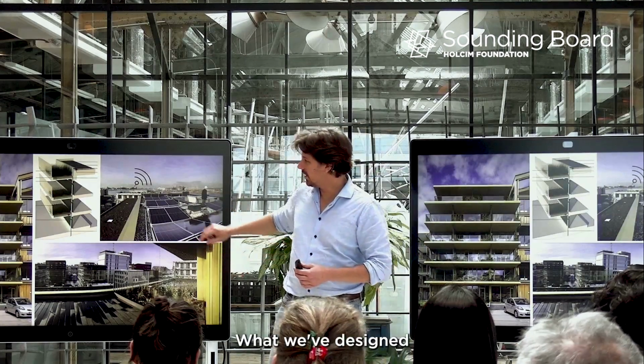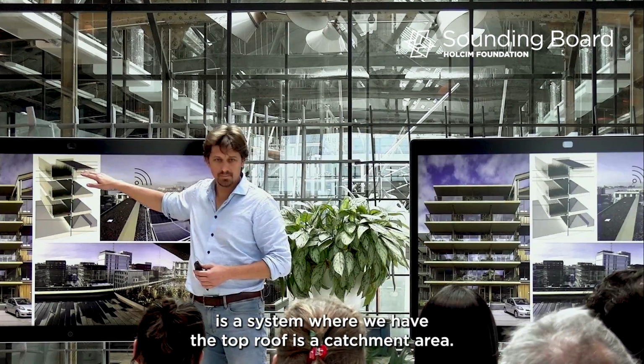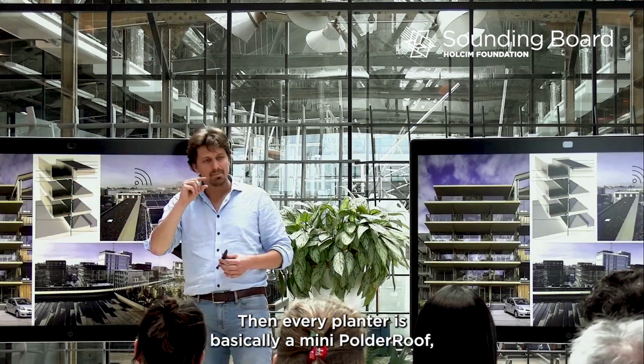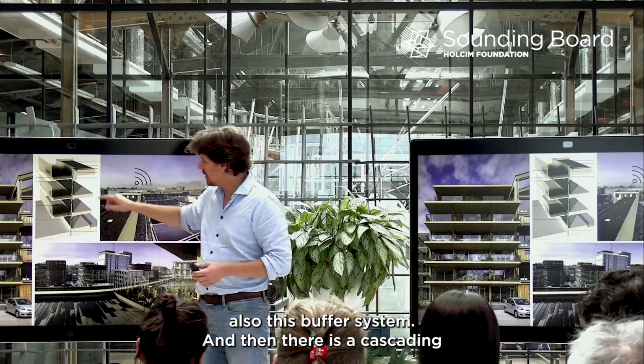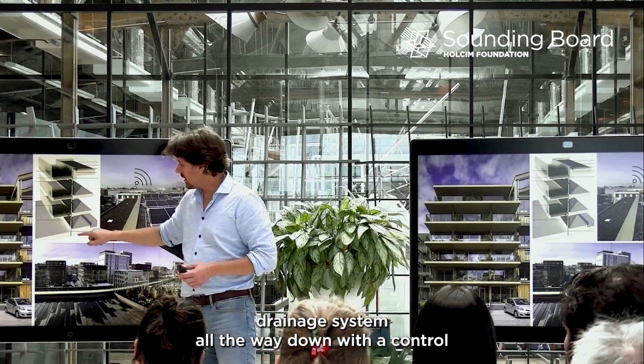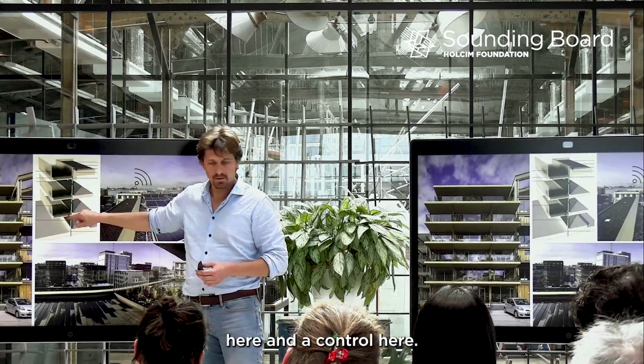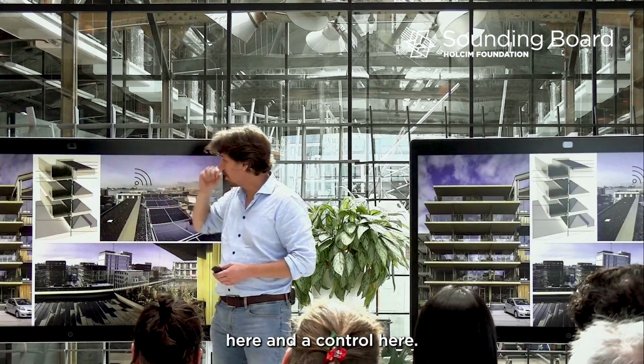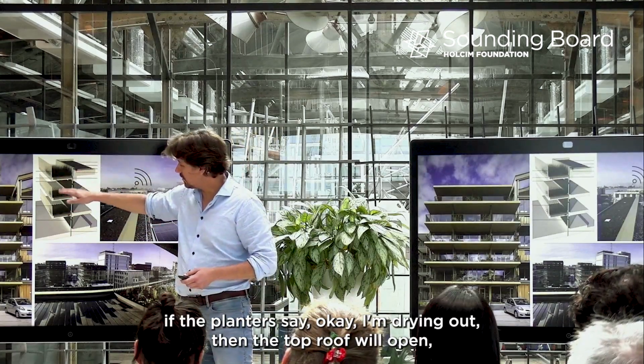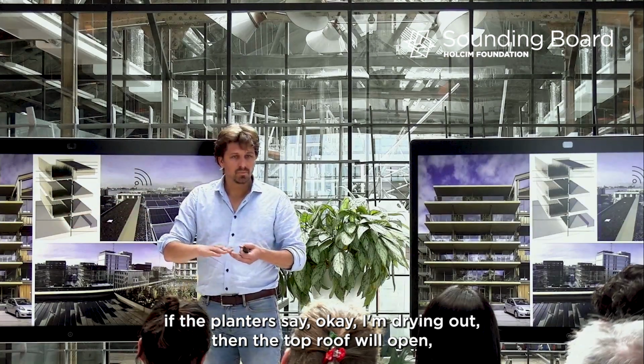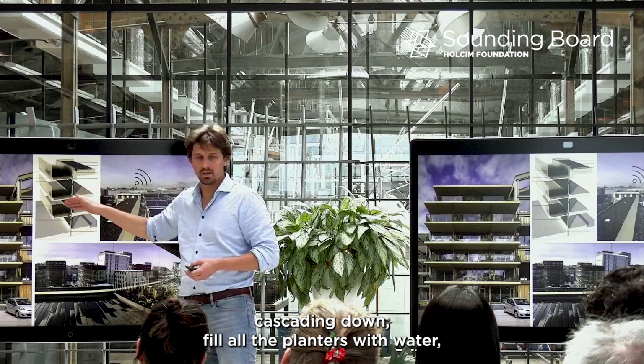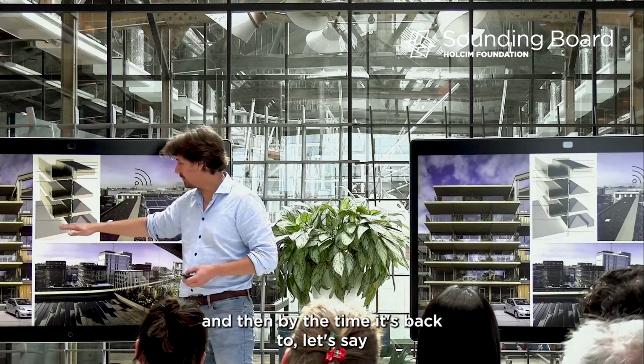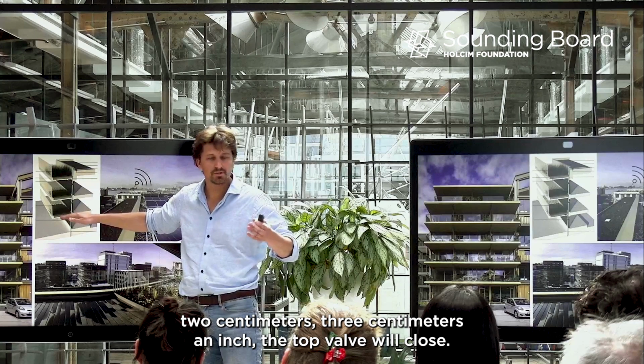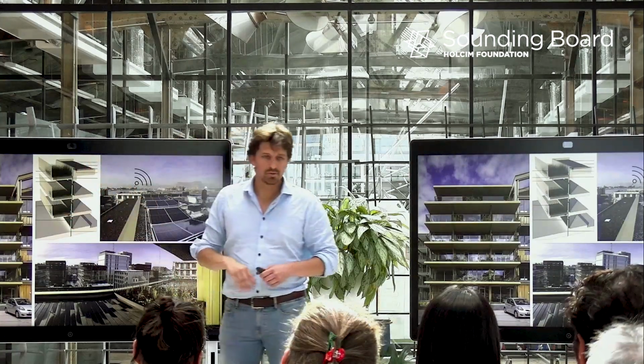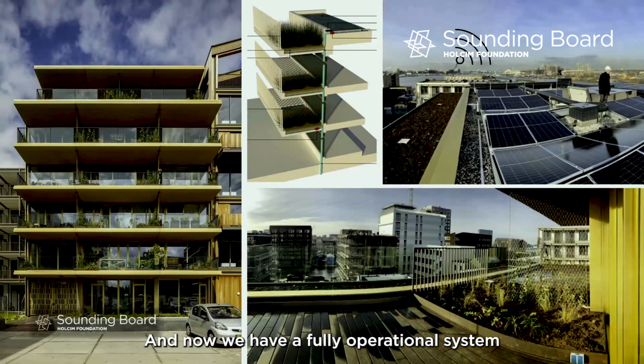What we've designed is a system where we have the top roof as a catchment area. Then every planter is basically a mini polder roof, so also this buffer system. And then there is a cascading drainage system all the way down with a control here and a control here. Basically how it works is if the planters say, okay, I'm drying out, then the top roof will open, cascading down, fill all the planters with water, and then by the time it's back to, let's say, 2 or 3 centimeters, an inch, the top valve will close, and now we have a fully operational system without any human interaction.